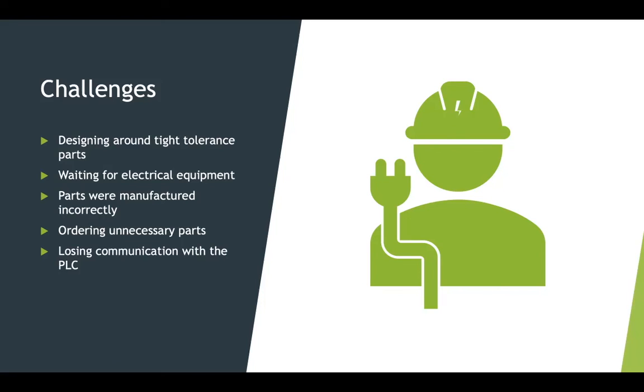Another challenge we did face was ordering unnecessary parts. We did order a couple wrong sensors and they had to be returned. However, they were able to be returned and did not eat up our budget. The last and most scary challenge we did face was losing communication with the PLC. This happened because the PLC serial IP address kept changing randomly and we were unable to find it. But we did combat that and we set a static IP address using an SD card and we were able to talk to it again. But that's our project. Thank you for listening and I hope you enjoyed it.